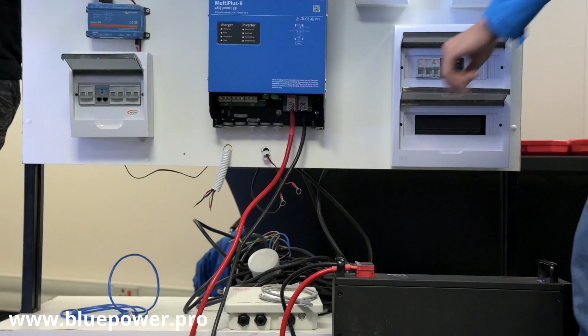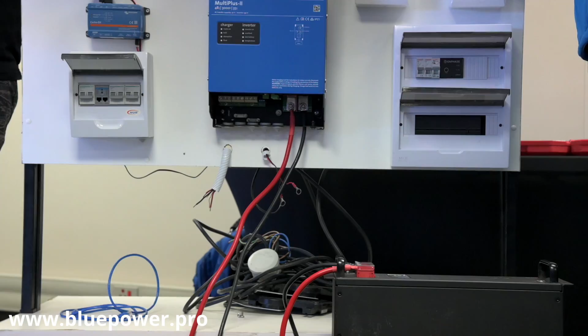So the BYD won't turn on if it doesn't have comms with the battery management unit. So it can pick up if there's no comms, and then it switches off. No, it will stay like that. It will only give out 5 volts. Okay. So you can test your polarity if you really wanted to, but the unit won't turn on. So you do require this box to be plugged in before your BYD is going to be switched on. So for that to communicate, I'll just use the supplied cable, and that plugs in on the BMS port. Yes, BMS port, and then on the battery out. Battery in. So on the battery in, but that will all be indicated in the BYD manual as well.